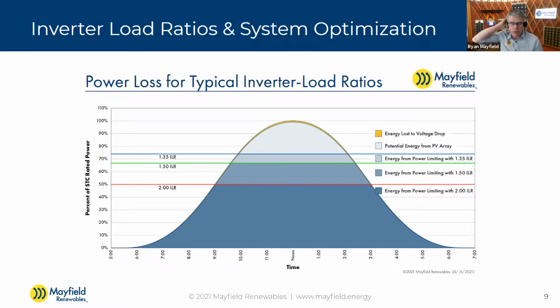Back to your earlier point — if you're AC constrained or interconnection constrained, say you can only do 5 megawatts of AC output, then you're power constrained, not energy constrained. Energy is what we're getting paid for ultimately, so you push those limits. I know you were mentioning some pretty aggressive pushing on those ratios too.